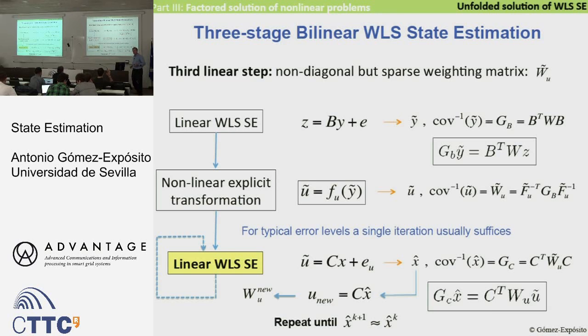But the first thing to do for this method is to try to find bad data errors and cut them out. Well, you don't need to do that. You can perform bad data analysis at the end, like in a regular estimator. But you now have the choice to perform bad data analysis here at the beginning, once you compute y. According to our experience, some bad data whose normalized residual is close to 3 may not appear here, but they will appear at the end. But those which are really bad data, with normalized residuals higher than 4 or 5, we also show here are larger than 3. So most bad data can, in practice, be detected and removed here. And there is no risk of divergence.